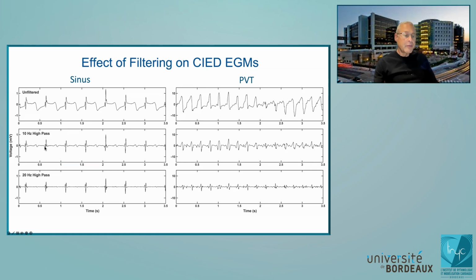So here's just an example of what happens when you filter a signal. You put a 10 hertz high pass filter in, T waves get a lot smaller, R waves get only a little smaller. Sinus rhythm R waves. With a 20 hertz high pass filter, R waves are a little smaller, T waves pretty much gone. Polymorphic VT, on the other hand, at 20 hertz, the R waves are down to a quarter the size of the baseline R wave, right? The unfiltered signal. So you really do lose a lot of signal in VF when you filter between 15 and 20 hertz. And that's why lots of pacemakers filter at 20 hertz or a little above that, but most defibrillators filter between 10 and 20 hertz. And the precise values depend on the company.